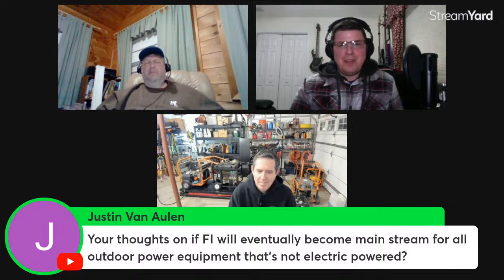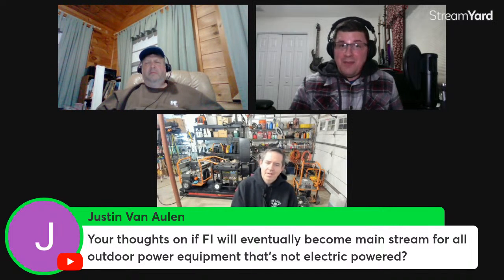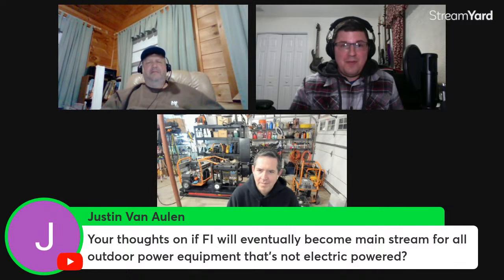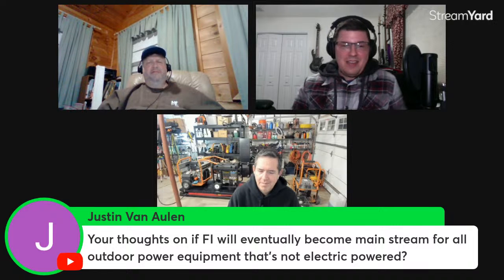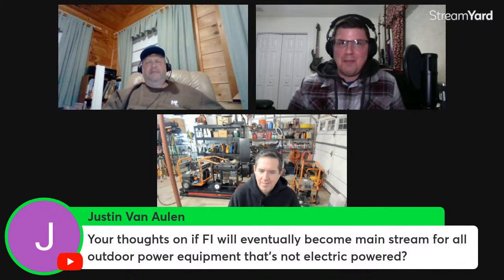And forget about the used market. Anything on the used market, if it's not an inverter generator, those big construction site type conventional generators, because of the output a lot of them are very dirty, high THD, that it's not practical for home backup power. It's more meant for a construction site, running a chop saw or air compressor, where those things don't really care if you've got 20 to 24% THD.